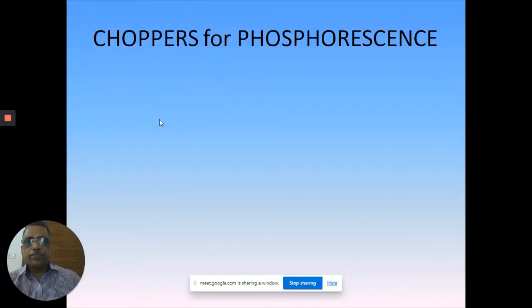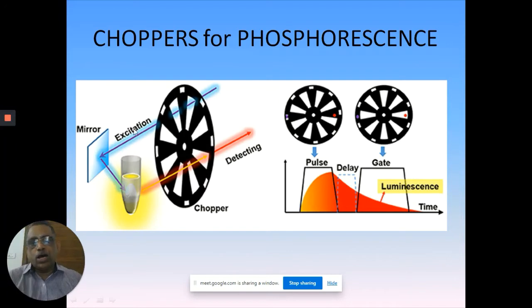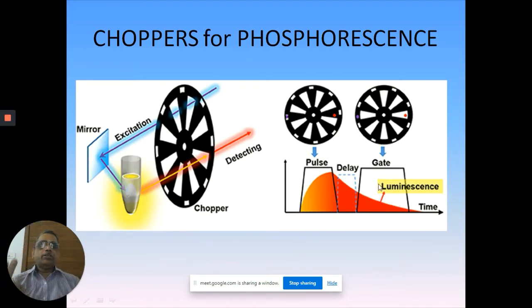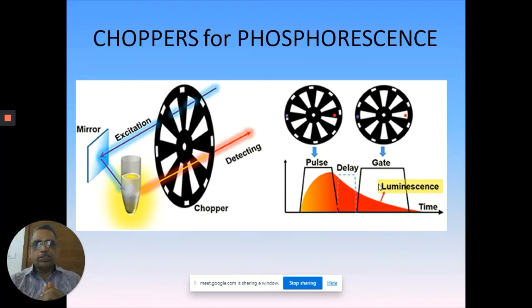This is the chopper mentioned earlier. You can use choppers to chop the light and make pulses. You can have a single chopper or a combination of two choppers. You can have chopping on the exciting light source or on the emission side. If you make a chopping on the excitation light source, you generate a pulse of light. When this becomes darker, you start measuring. Luminescence will decay in this time, and you can gate the detector using a disc. So pulse the light source and gate the detector - this is possible with two discs.